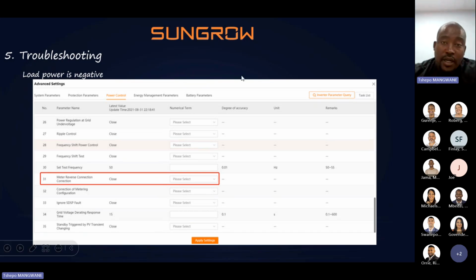Okay. So how do we correct the CT if you are not on site? You just log in remotely on your cell phone or PC. Go to advanced settings, select power control, then scroll down to meter reverse connection correction. The moment you enable this setting, it will change the meter to read in a positive direction. Right. There's no need to drive back to site.